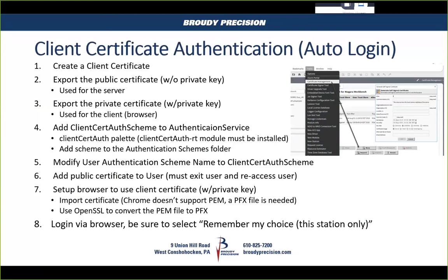But basically, there's your certificate management tool in Niagara, where you're going to create your certificate, your client certificate, and you're going to be exporting it twice, once with the private key and once without the private key.